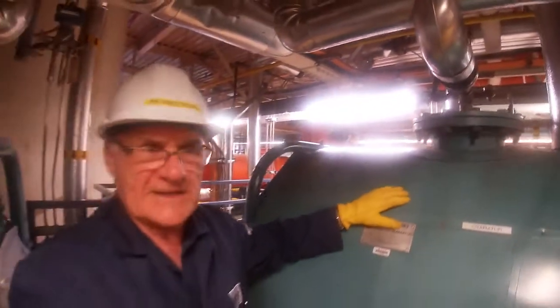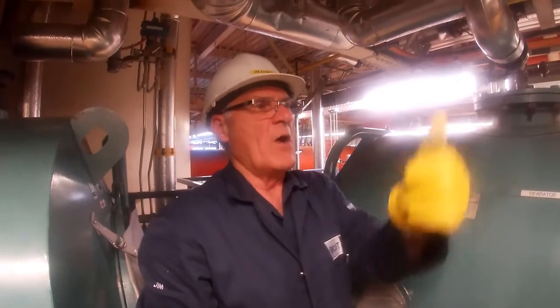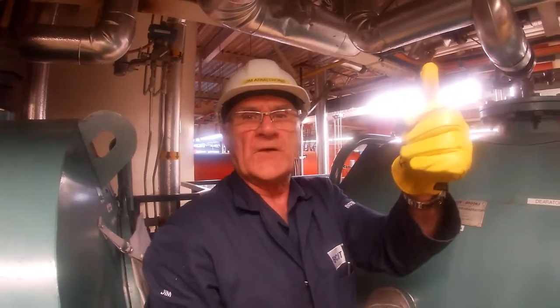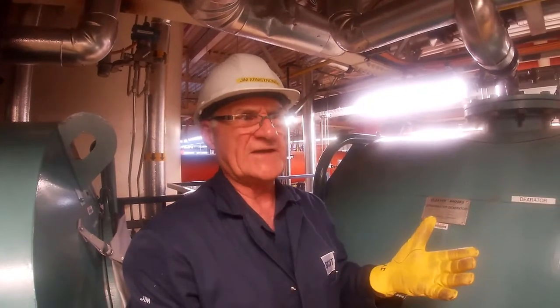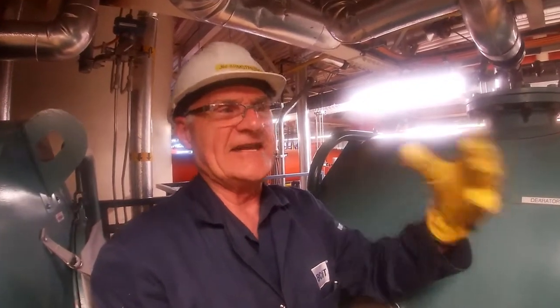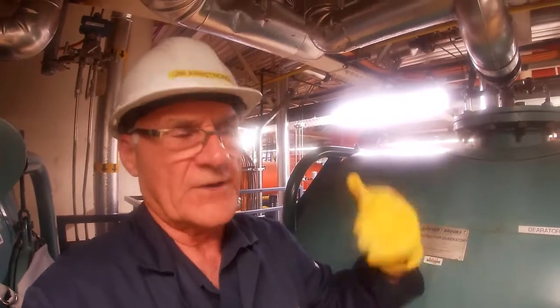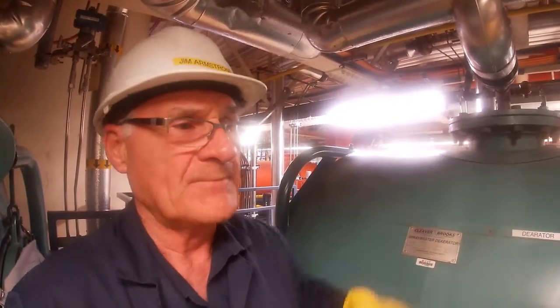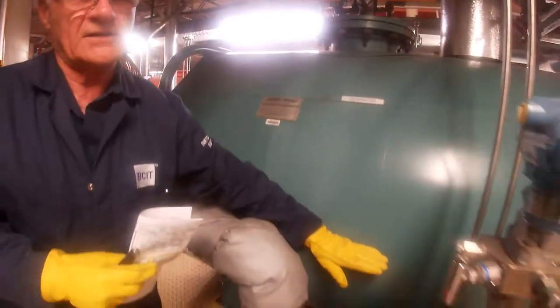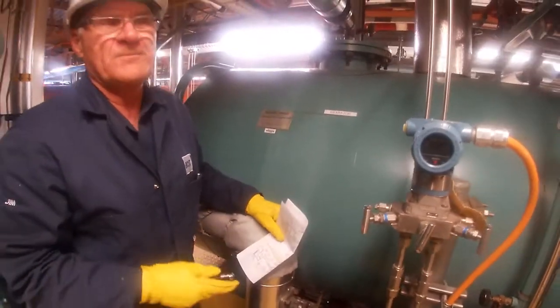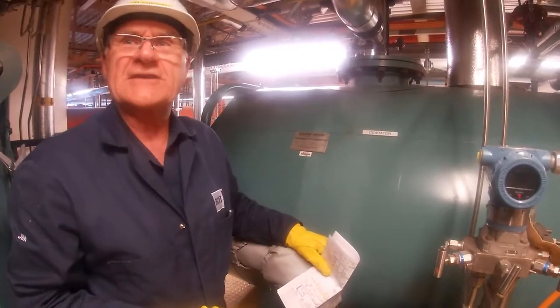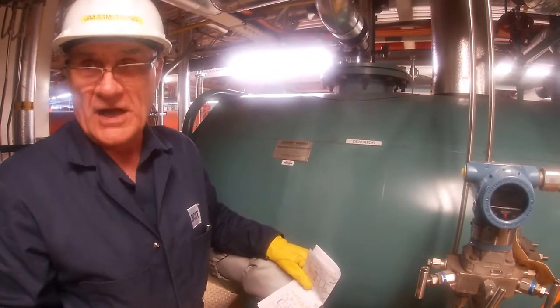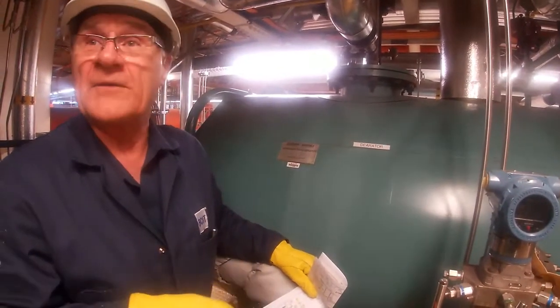So in a running steam plant, you would see a small vapor stream coming up from the roof all the time, and you might think that's wasteful, but in fact that is the deaerated water, or the vapor that's coming out the top, getting rid of nitrogen, oxygen, and all kinds of other gases that we don't want in our water. The water down in the vessel will be somewhere in the order of 5 to 7 parts per billion as dissolved oxygen. We need to get that oxygen level down very low.